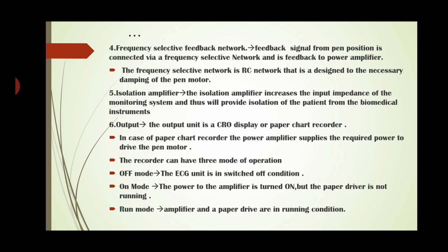Frequency selective feedback network. The feedback signal from the pen position is connected via a frequency selective network and fed back to the power amplifier. The frequency selective network is an RC network that is designed to provide the necessary damping of the pen motor.